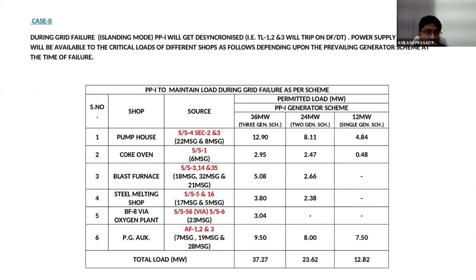Suppose it is case 2, where the grid has failed. During the grid failure, in islanding mode, PP1 will get desynchronized. That is, tie lines 1, 2, and 3 will trip on df by dt. And power supply from PP1 will be available to the critical loads of different shops as follows, depending upon the prevailing generation scheme at the time of failure.